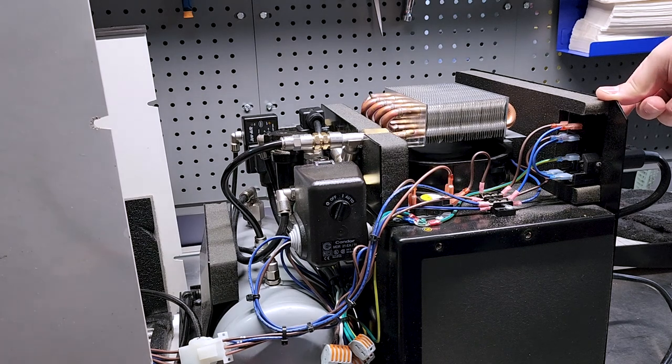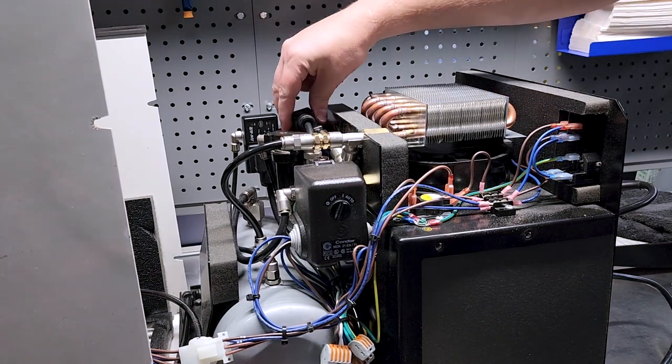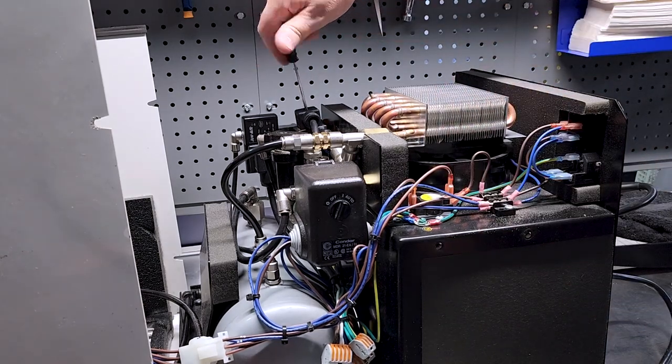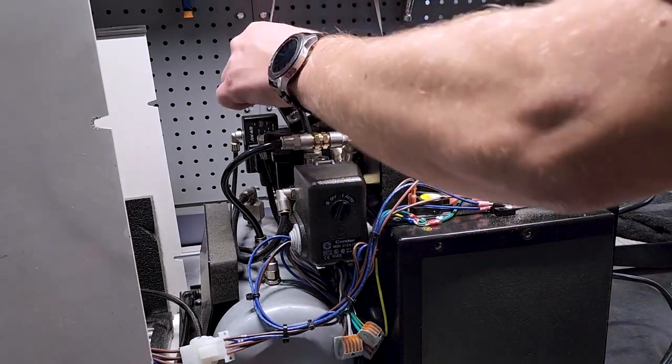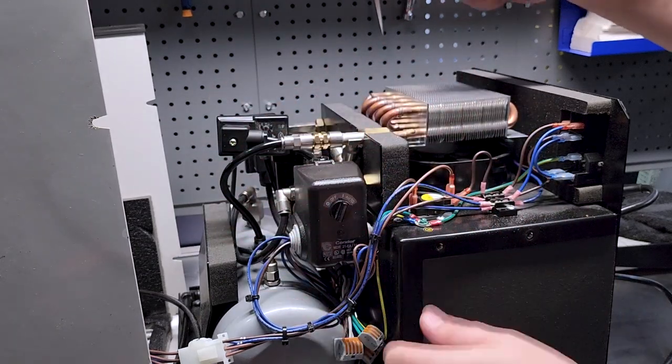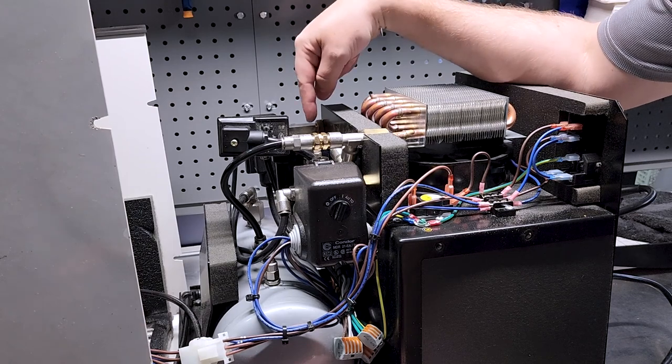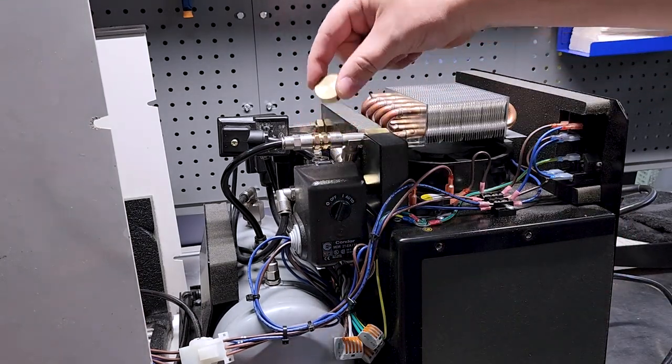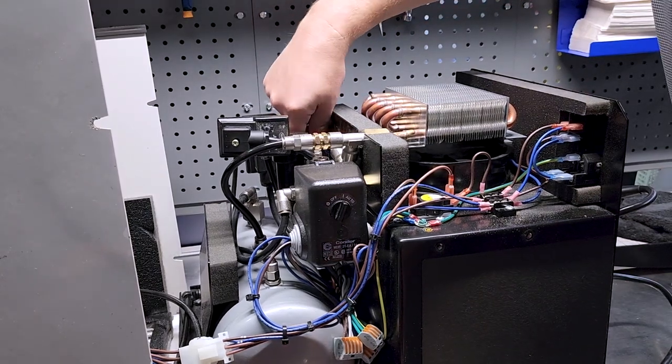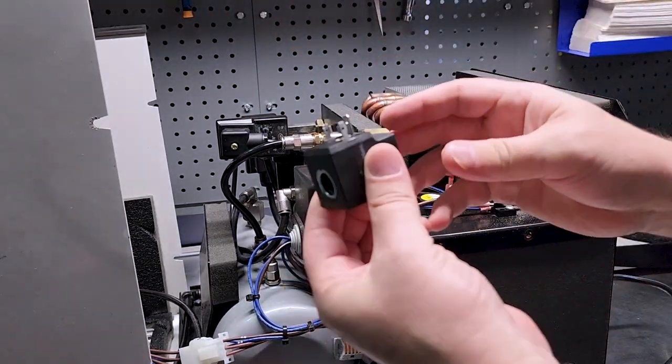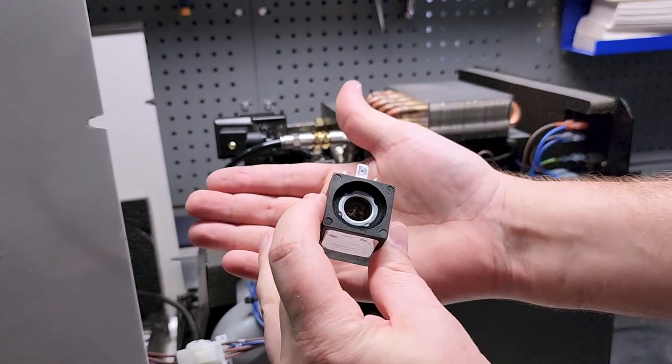So I want you to pay attention to the sound it creates when it's powered up because there is something going on right here and I will show you what's going on in just a moment. Hear that? So that's not typical solenoid vibrations. There is something else going on there. And for safety sakes, let's go ahead and disconnect this guy. This guy right here, believe it or not, I've already gone through and seen what's really going on. So let's go ahead and disconnect this relay. This is the auto purge solenoid. So let's go ahead and disconnect him, sit him off to the side. So this guy here is just a plug. It's just an interface with the timing mechanism. Doesn't really do very much. The physical piece is actually done by the solenoid coil, which is down here in order to remove that. We have a cap, which is a retainer. I pull that cap off and then the solenoid valve body or the coil itself just kind of slides off.